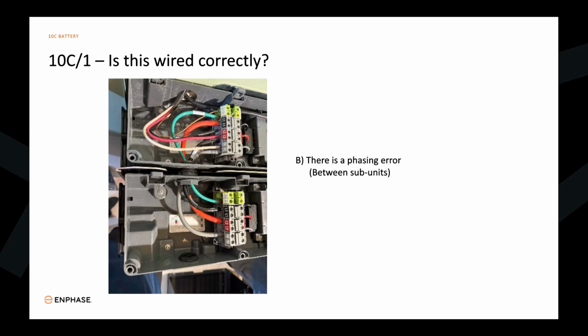But if you simply look down at the bottom battery, look at the blocks, and know your colors, that looks good. It's kind of hard to trace through the raceway, I understand that. But if you look at the blocks up top and see where the wires go in, you have ground, line 1, line 2, and neutral. You should clearly see there's a phasing error between line 1 and 2 up here at top, where they didn't follow the phase switch and actually went phase to phase.